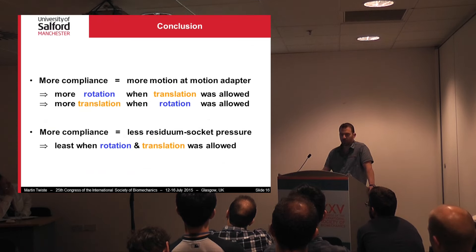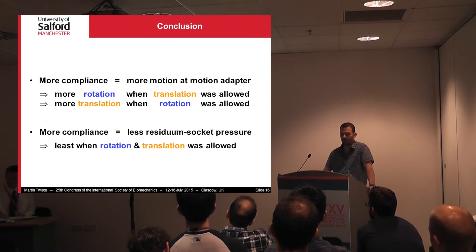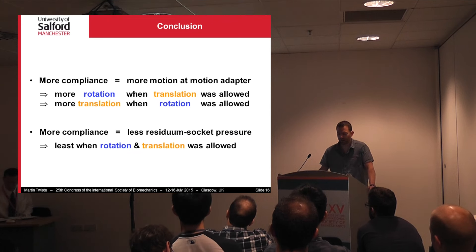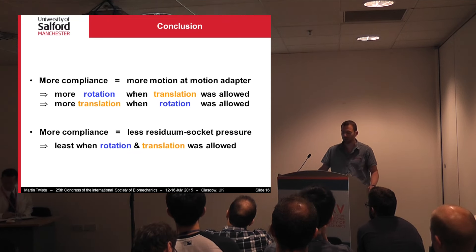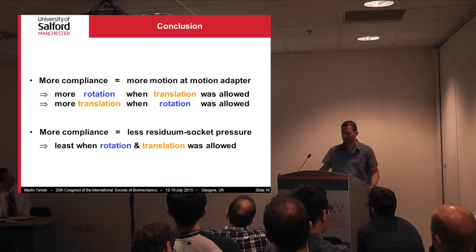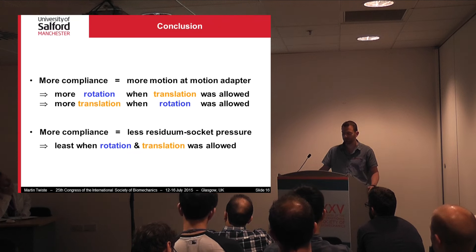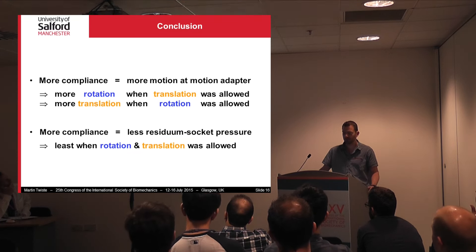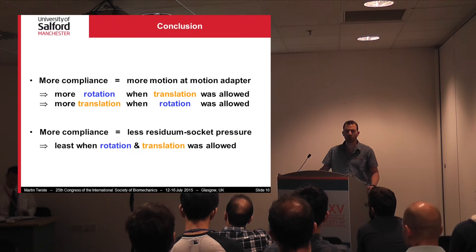In a nutshell: more compliance means more motion at the motion adapter, and more compliance also means less residual-socket pressures.